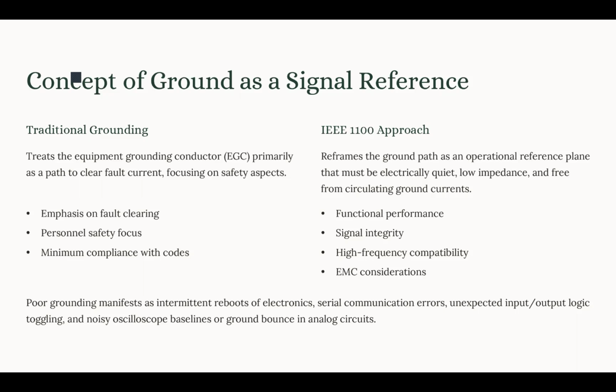Now, there is a limitation for sensitive electronic equipment, which is that traditional safety grounds can be electrically noisy. Why? Because we have circulating ground current induced by other nodes, or we have an impedance that is too high when we talk about high frequency transients. This results in logic errors, random resets, serial communication faults, and data corruption.